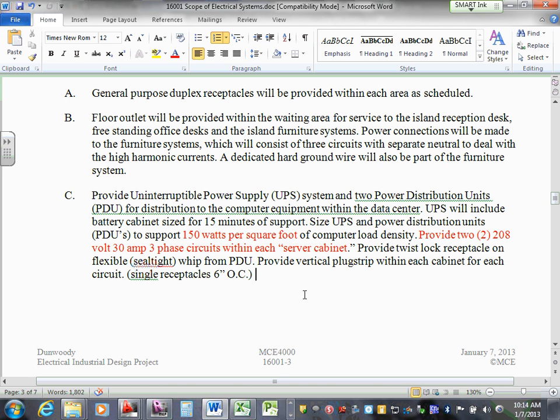There are different power factor issues as you go through the UPS and look at your amps coming into the UPS, depending on the power factor of the UPS module. But it's going to affect you more at the UPS than on the floor.